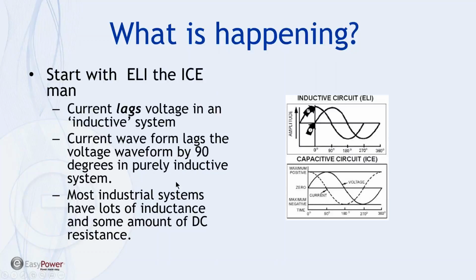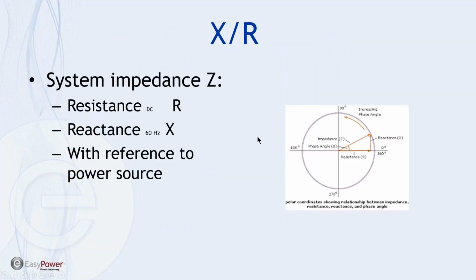Now, most industrial systems have a lot of inductance and some amount of DC resistance in the form of a cable impedance and the like. And so very seldom do you find a purely inductive system in real life. And so there's a measure or a comparison of the inductance, inductive reactance, compared to the DC resistance, and we refer to that ratio as X over R.